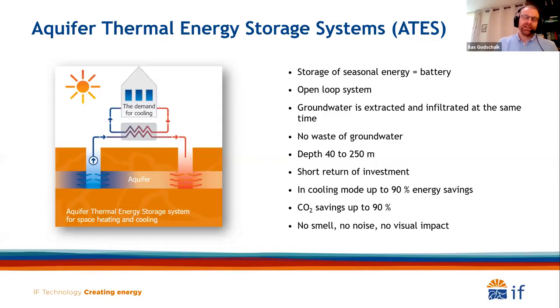Thank you. From the 7 degree well, we abstract the cold water. We exchange it using a heat exchanger, and the heat from the building is transported to the water, while cold is provided to the building. Then the warm water is re-injected into the warm well at about 17 degrees. So the warm well becomes about 17 degrees, and during wintertime you abstract from the warm well to heat the building, and charge the cold well by injecting the cold water.